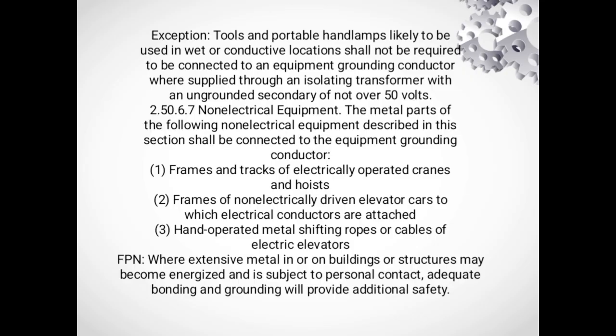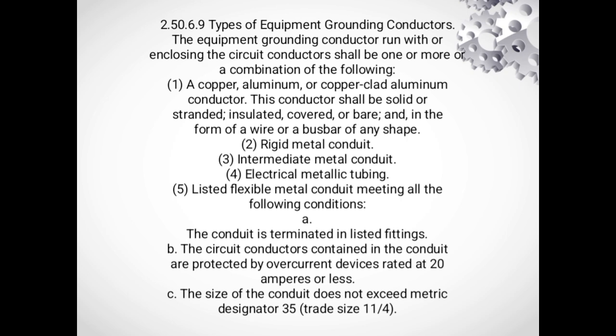Not everything needs to be grounded. Double insulated equipment or distribution apparatus high up on poles might be exception. This slide clarifies these edge cases. 2.50.6.9 Types of equipment grounding conductors.